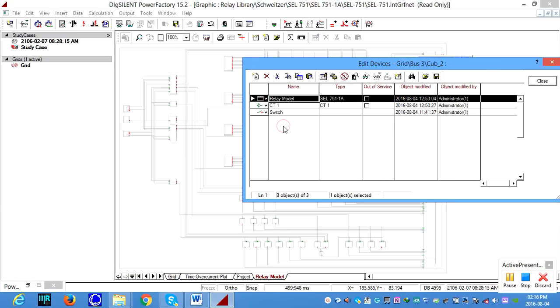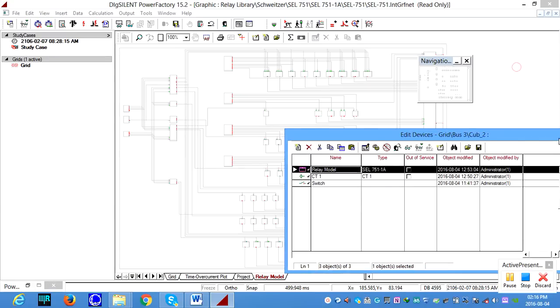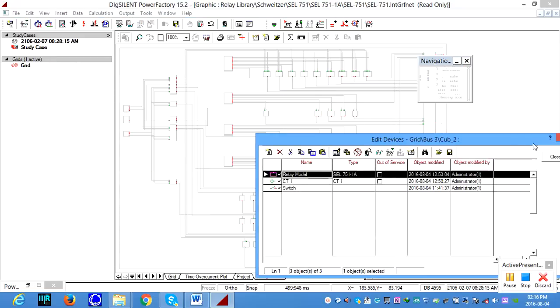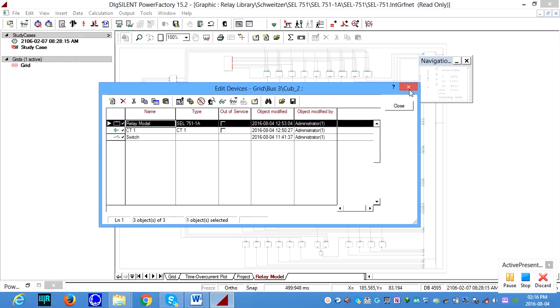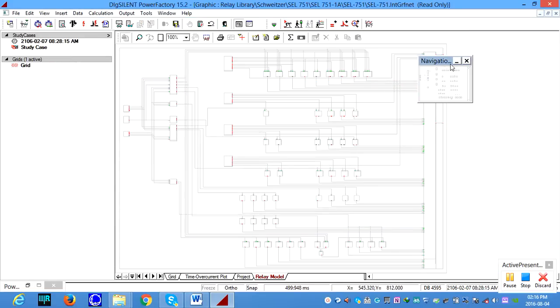The show graphic will show you the relay wiring diagram. I think I can close this one quickly. So this is a navigation panel that will show you the relay wiring diagram. This one shows all the CTs and PTs, because the relay has hardware with specific components that are wired inside the relay, and this wiring diagram will describe it.